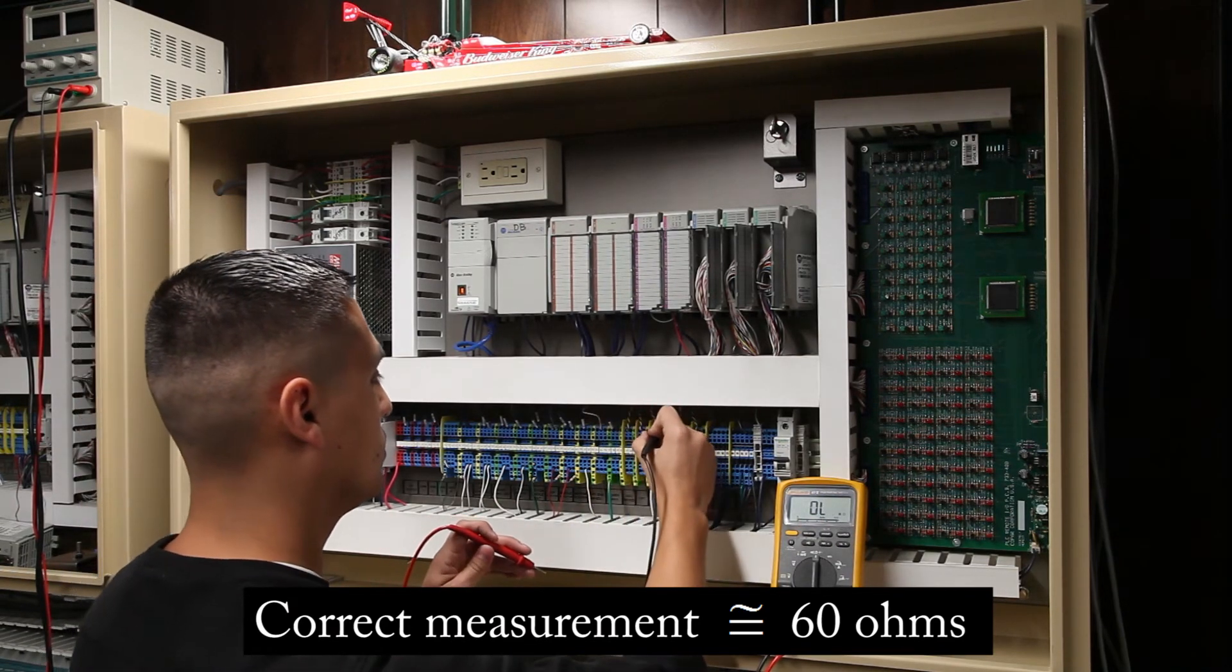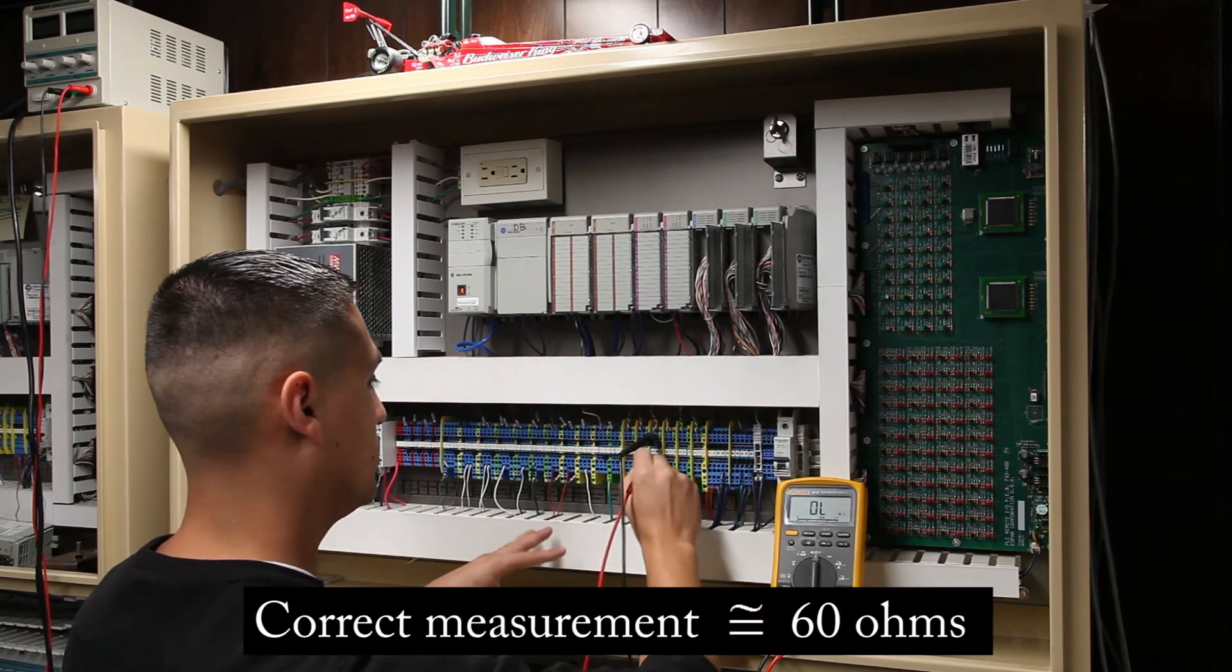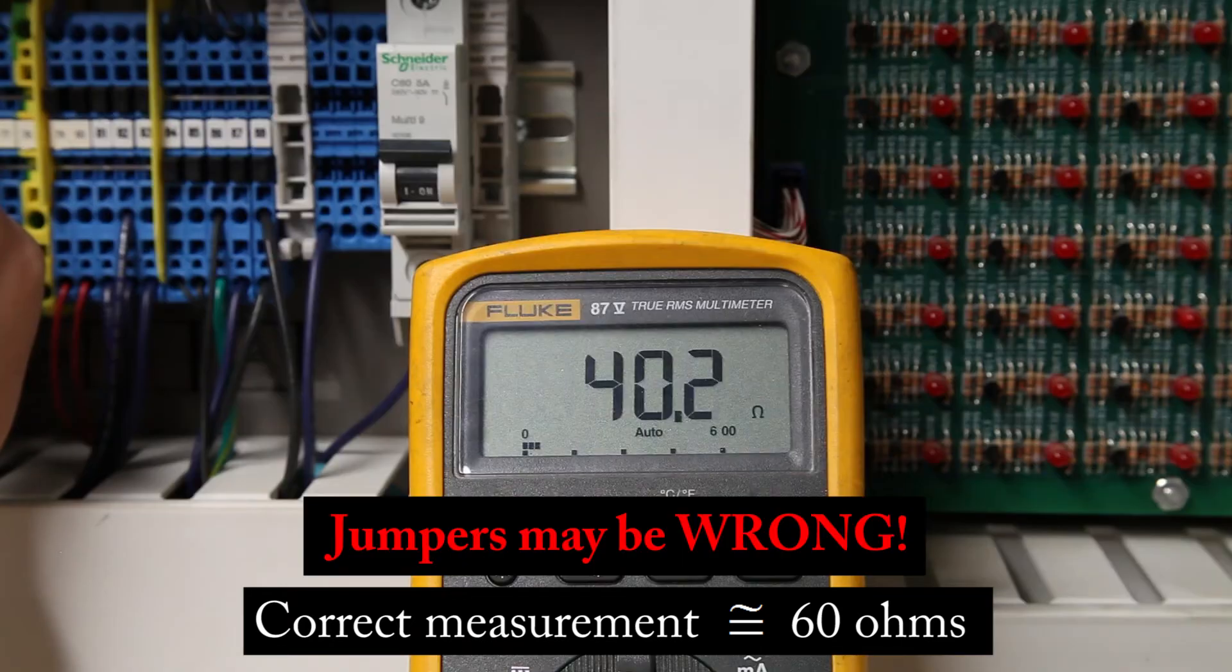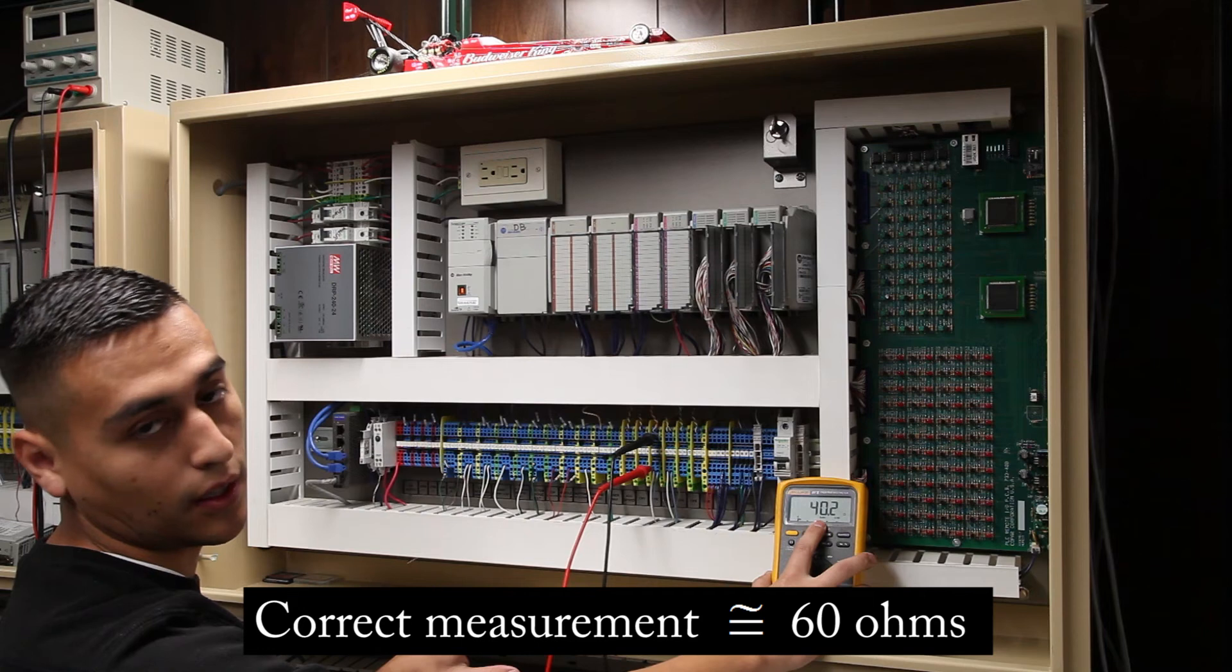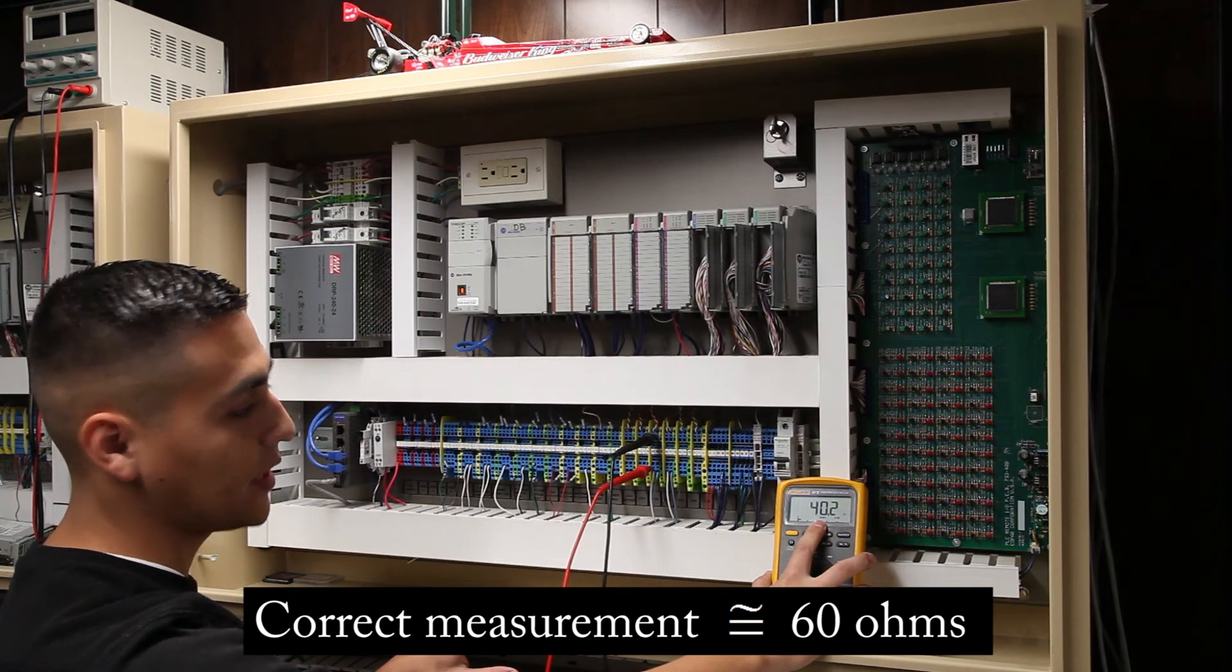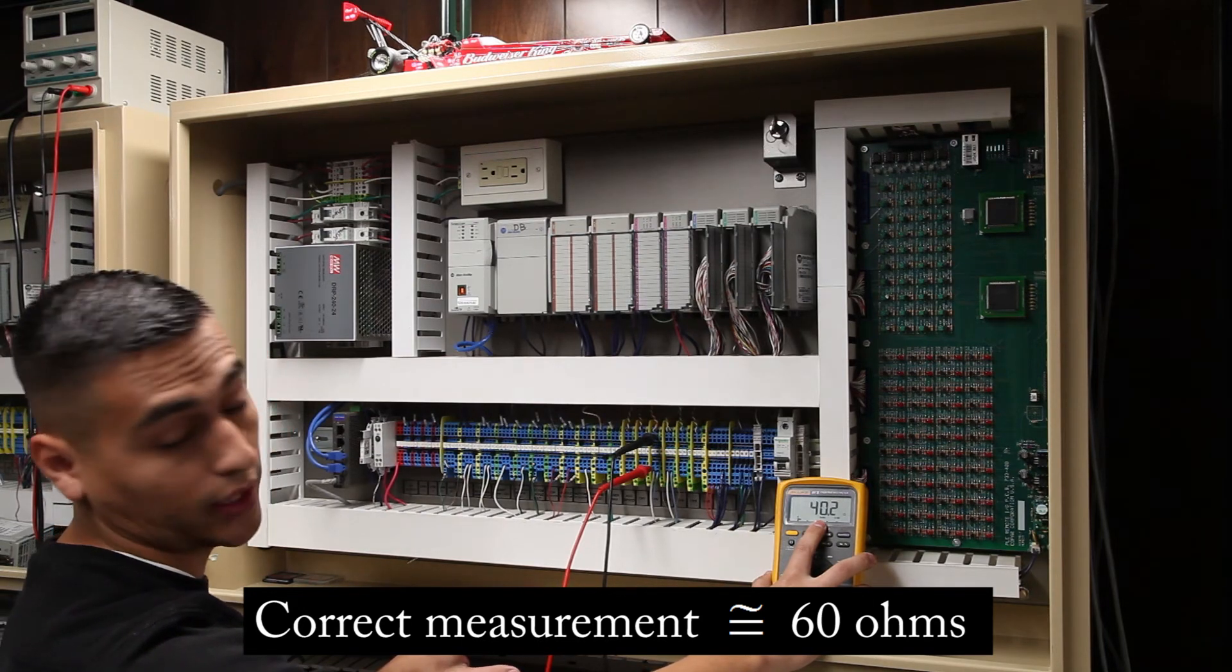On a bad channel, we get a reading of 40 ohms. We shouldn't see that. Again, what we should be seeing is 60 ohms with that terminating resistor at the end of the last string on the D-Net channel.